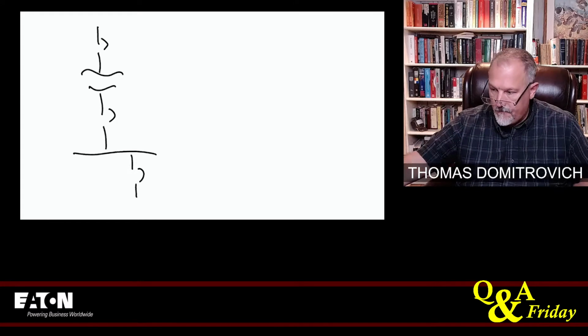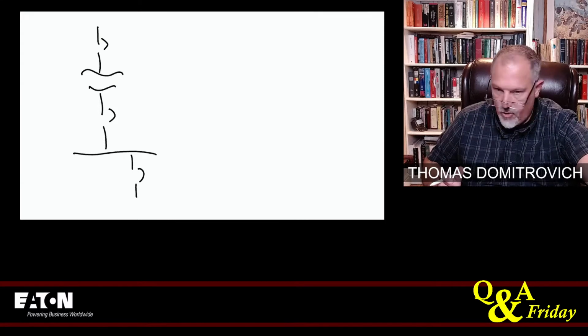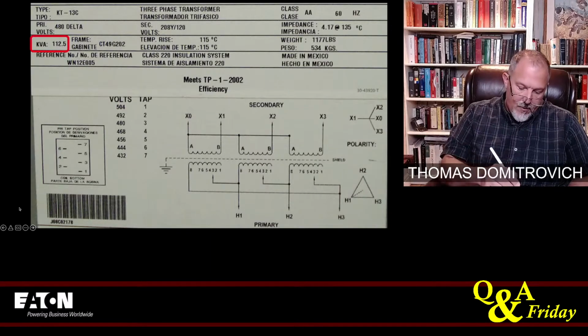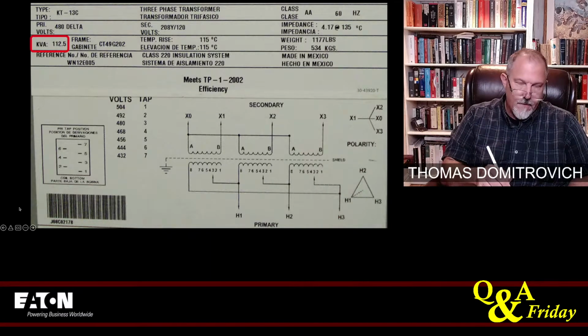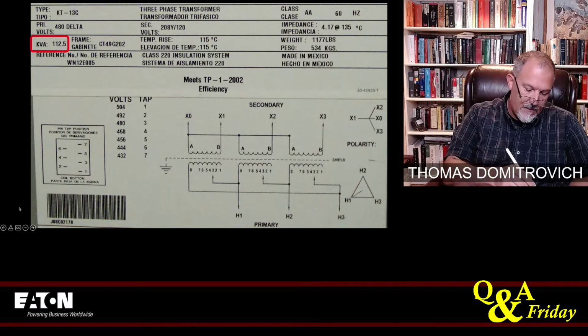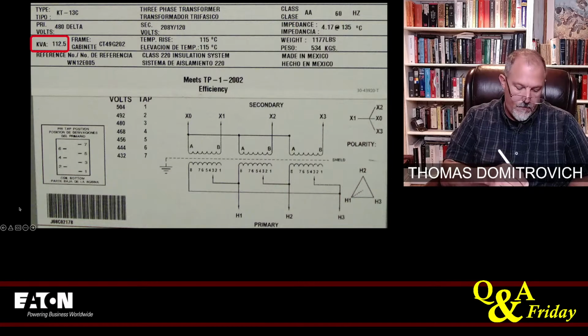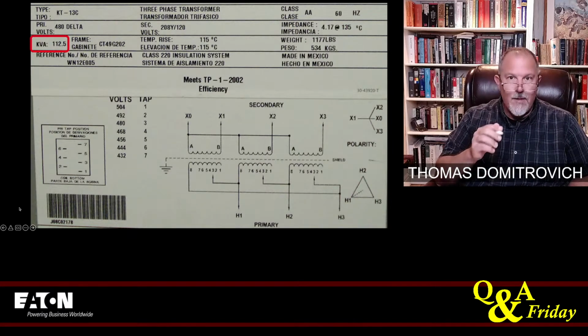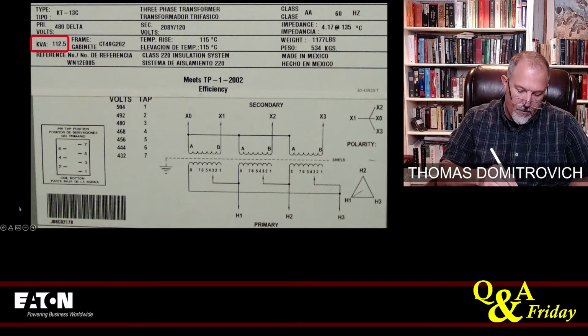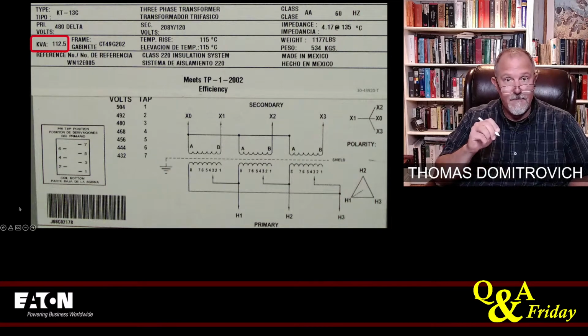I'm looking for the nameplate. All right, here we go. So what we have is a 112.5 kVA transformer, primary 480, secondary 208. We have 4.17% impedance. And I think that's all we need with regard to that.